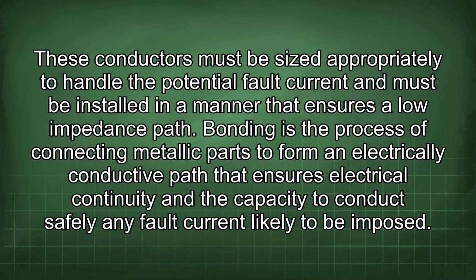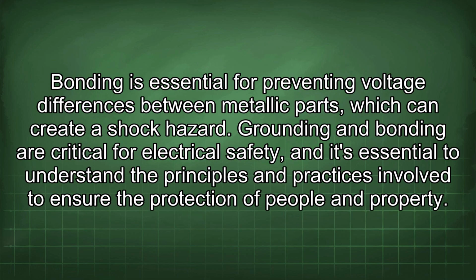Bonding is the process of connecting metallic parts to form an electrically conductive path that ensures electrical continuity and the capacity to conduct safely any fault current likely to be imposed. Bonding is essential for preventing voltage differences between metallic parts, which can create a shock hazard.